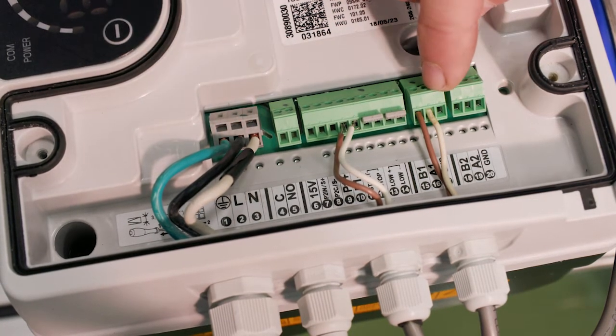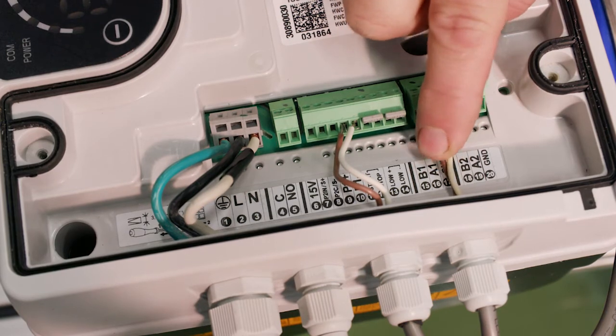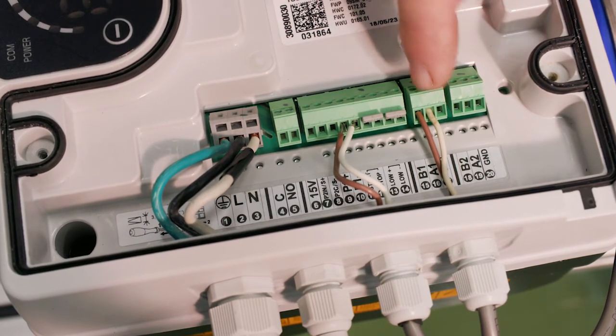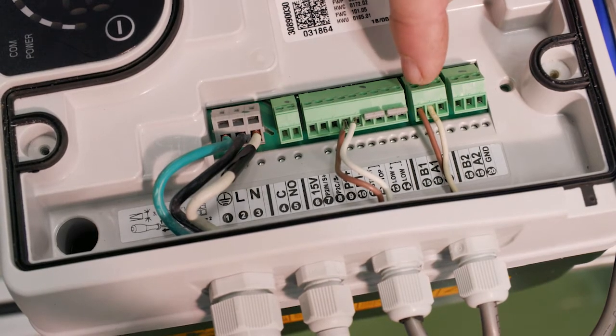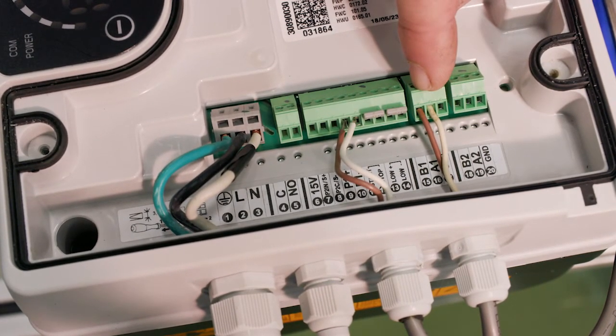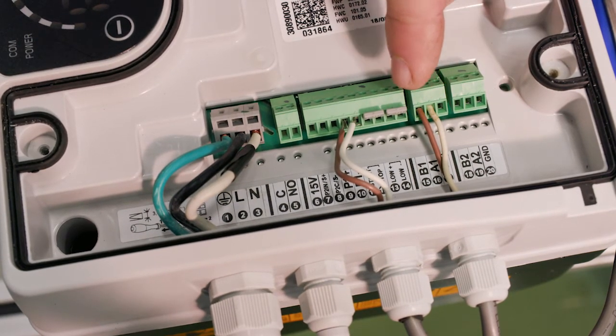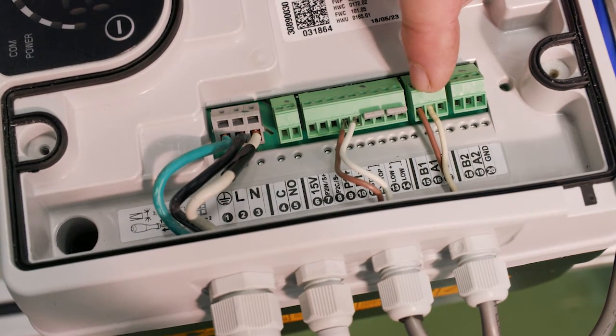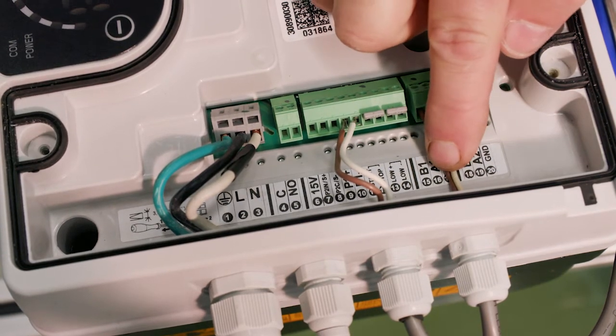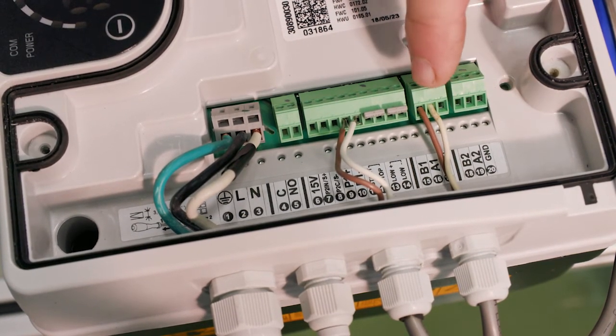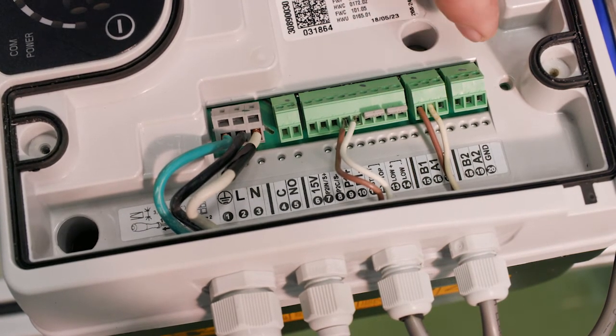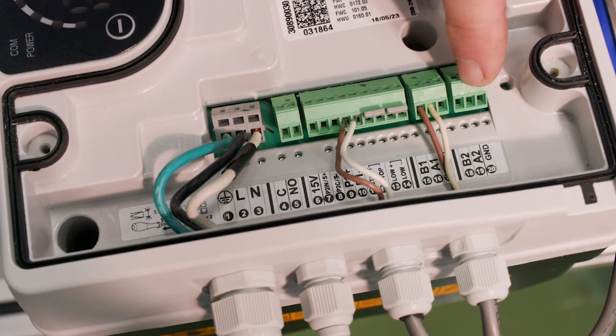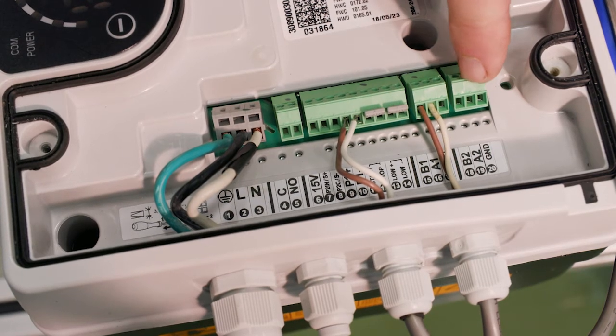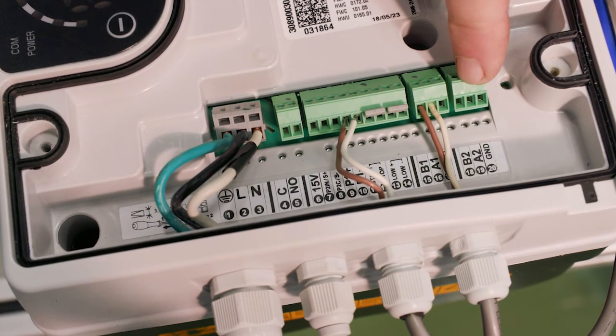The only other 2 wires that we need are right here, terminals 15 and 16, and that is our communication port. We have the exact same wiring on the other drive. If we've got brown on terminal 15 for this drive, we want brown on terminal 15 on the other drive. The same thing with the white: the white is on 16, so make sure it's on 16 for the other drive. We are not using the extra set of the communication port. As a matter of fact, you need a separate module in order to use those terminals.